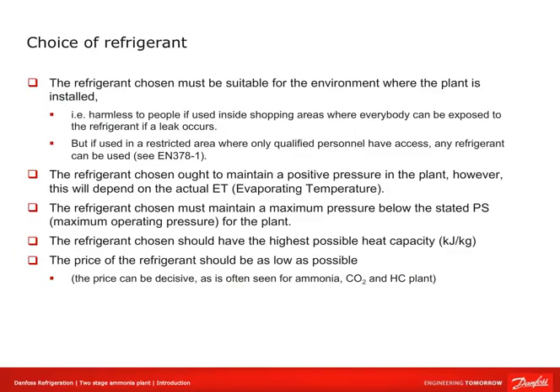The refrigerant chosen must be suitable for the environment where the plant is installed — harmless to people if used in shopping areas where everyone can be exposed in the event of a leak. If used in a restricted area where only qualified personnel have access, any refrigerant can be used per EN378-1. The refrigerant must maintain positive pressure in the plant, a maximum pressure below the stated PS maximum operating pressure, the highest possible heat capacity, and should be as low cost as possible — as is often decisive for ammonia, CO2, and HC plants.